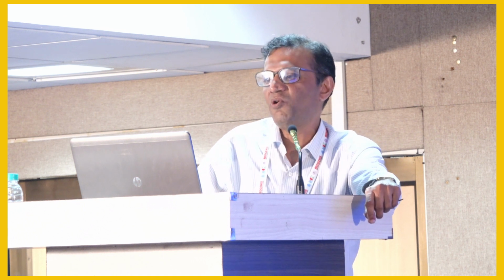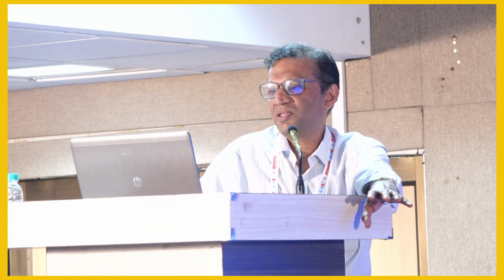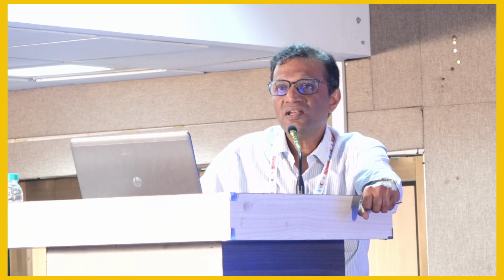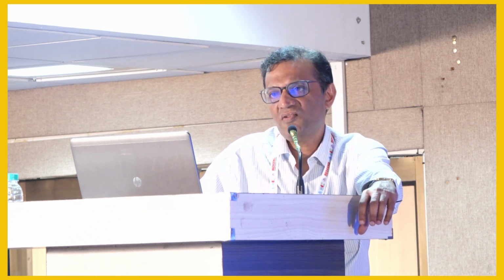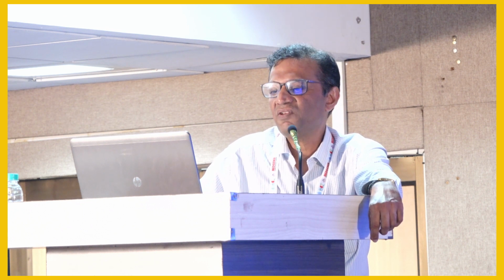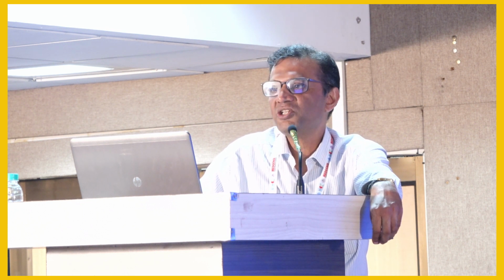My last bit is about machine safety. A truly safe machine should be fail-safe. That is, single fault dysfunction should be picked up, and a truly fail-safe device should not allow us to override it either manually or by an electronic signal. It's done with the help of redundancy and watchdog circuitry. The watchdog test is what the machine tests when we first put it on. A safe mode of operation means the patient should be isolated from an unsafe machine. It stops the blood pump, clamps the line, preventing blood which could be potentially dangerous from returning to the patient.